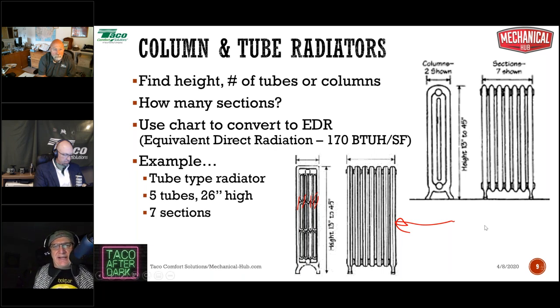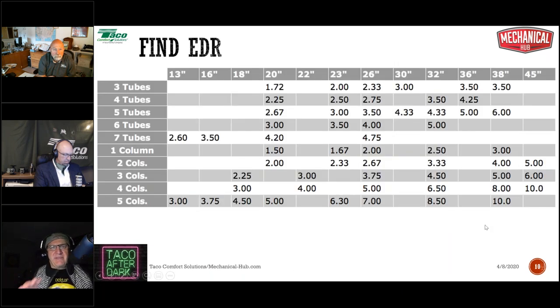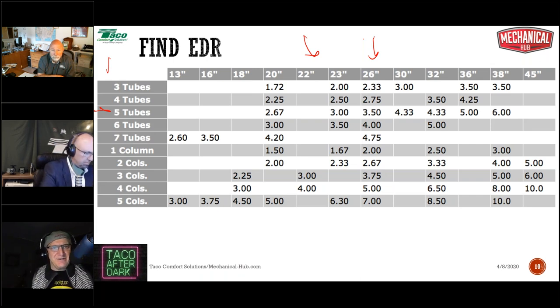Let's take a look at this chart. Now, this chart is also in the Burnham Heating Helper, and it's for tubes and columns. Up at the top, we have the height, and over here on the left-hand side, we have from three to seven tubes and from one to five columns. So we presume that this was a five-tube radiator, 26 inches high. You can see the way these are populated. These are the most common sizes.